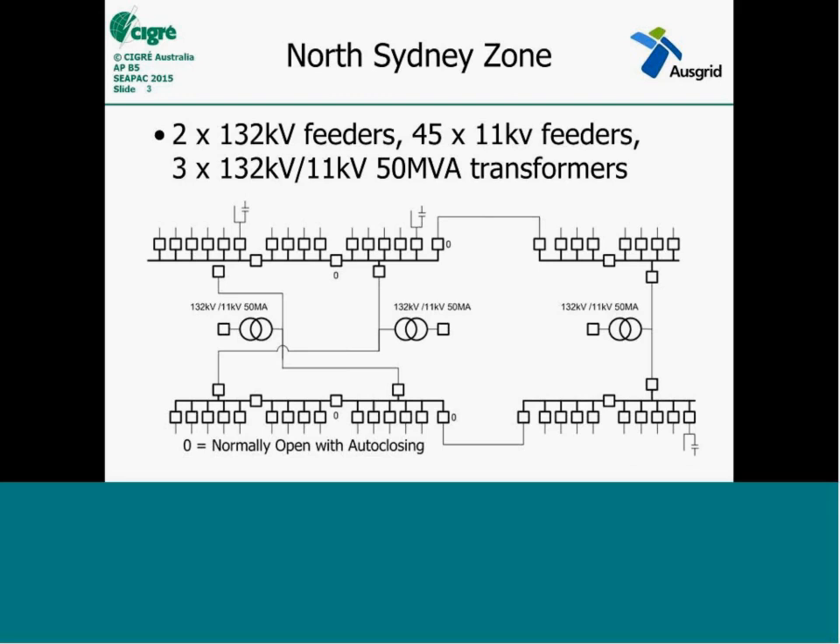Within 61850 we decided on select-before-operate controls. We decided we didn't really care whether the currents were a few amps higher or lower in the last few seconds if we missed a packet — what really mattered to operators was what the currents are now. We've also got full fault record file transfer through 61850 from the relay, sent to the local RTU/SMU and then transferred to head office. Within 15 minutes the synchronisation happens, so it's fully available to anyone in the company through a web page. We also implemented under-frequency load shedding through peer-to-peer GOOSE messaging.